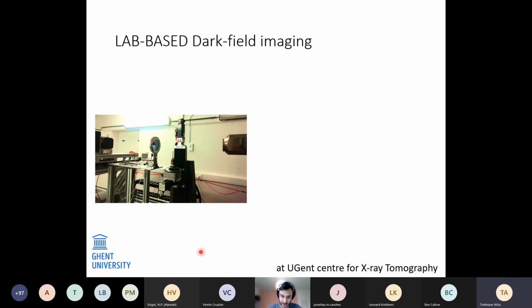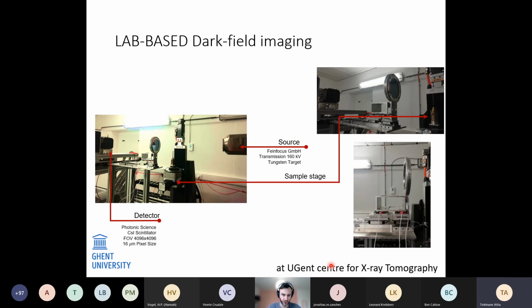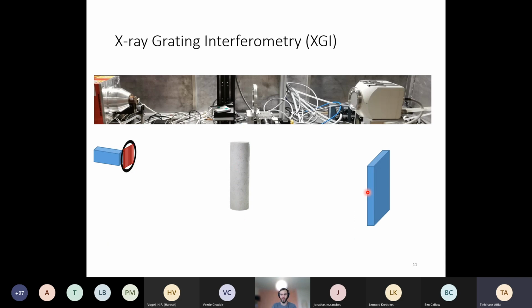So it is still micro CT. So you have all the conventional elements of a micro CT imaging system. You have your X-ray source, you have your detector, you have your sample on an automated stage, and that's a crucial novelty in this type of imaging. You have gratings. Now these gratings, you can think of them as being these very fine line structures, and there's two of them, and you place them in between your detector and your sample. That's one way to arrange it anyway.